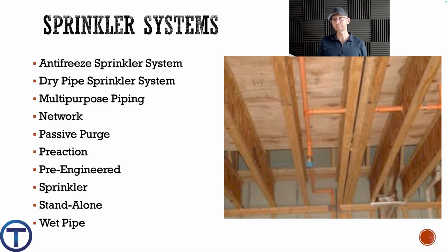Finally, a wet pipe sprinkler system employs automatic sprinklers attached to the piping system that contain water and connected to the water supply so that the water discharges immediately from the sprinklers opened by the heat from a fire. Yeah, basically it's always got water, and as soon as those heads pop, water is delivered.